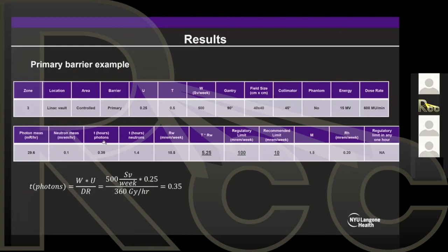What is the time, right? Because we need to multiply this factor by the time. So here I put how I calculate the time, right? You're going to have your workload, so you have it up here, 500 sievert per week. You're going to multiply by the use factor, so how much of those sievert are actually going to be delivered in that direction. And then you're going to divide by the dose rate. This is just 600 MU per minute, where I made an equivalence of 1 MU, 1 centigray, and I moved to hour instead of minute. So we get an average time on of 0.35. So I plug it there.